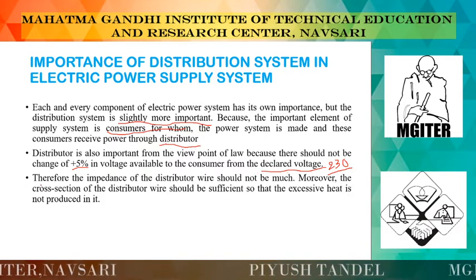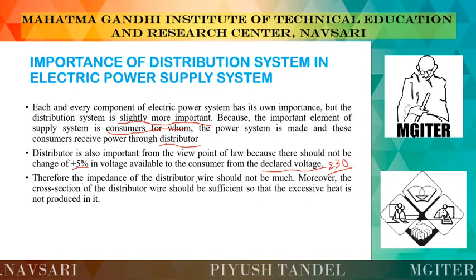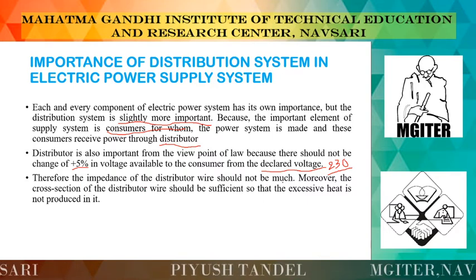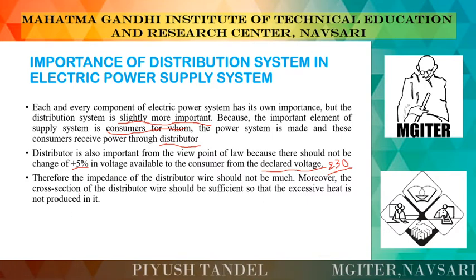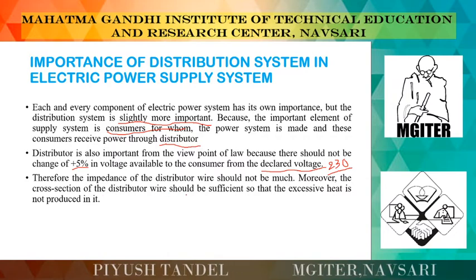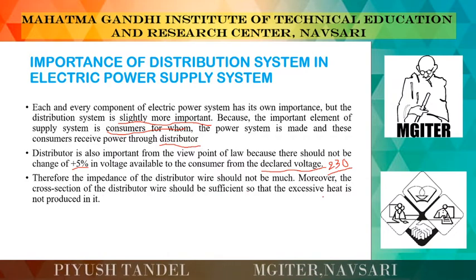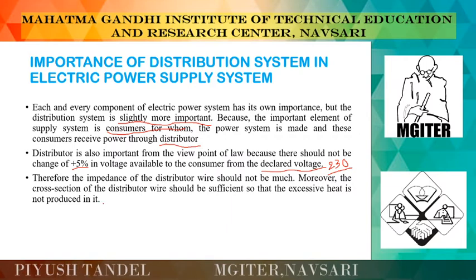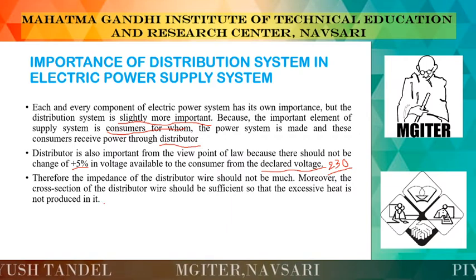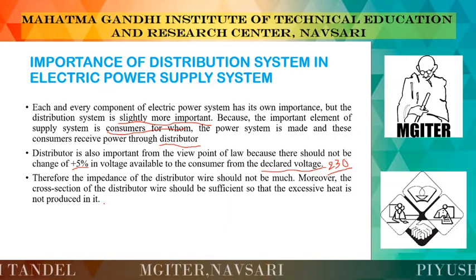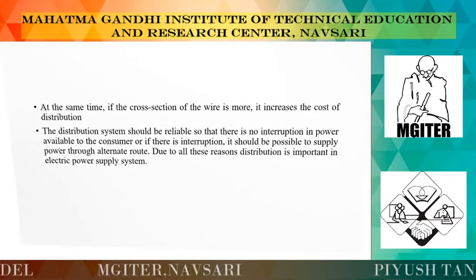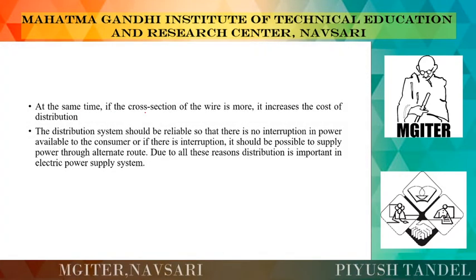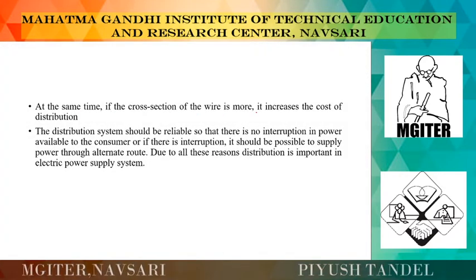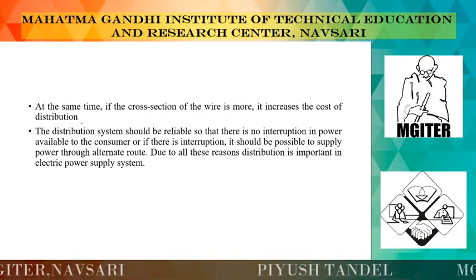Next, the impedance of the distributor wire should not be much. Moreover, the cross section of the distributor wire should be sufficient so that excessive heat is not produced in it because of the large amount of current flowing through the distributor. At the same time, if the cross section of the wire is more, it increases the cost of distribution.